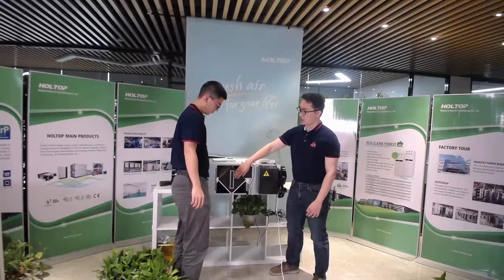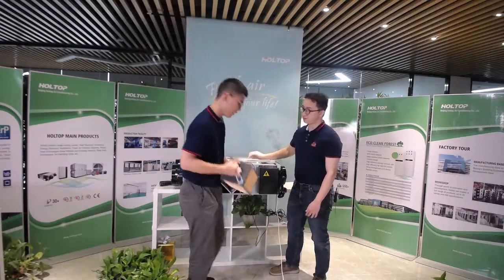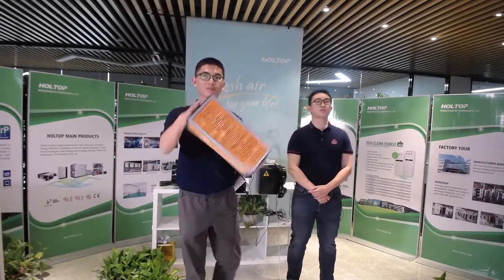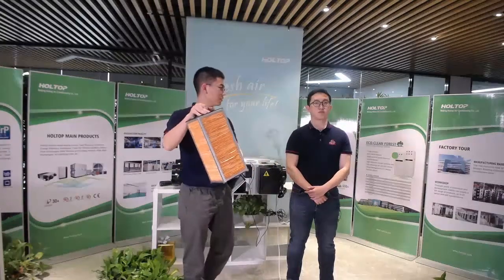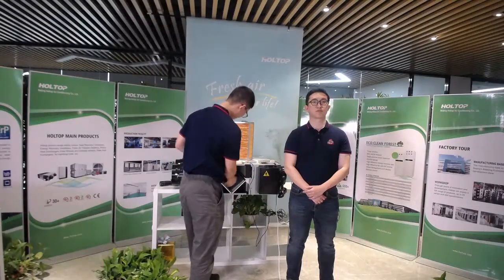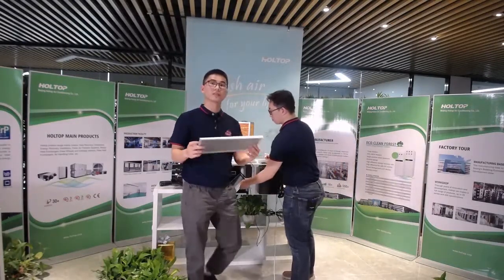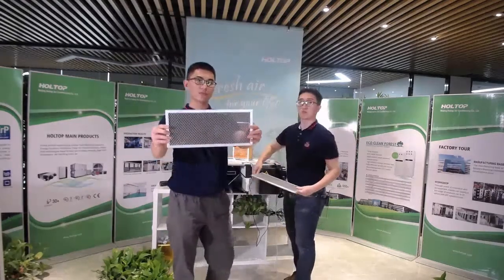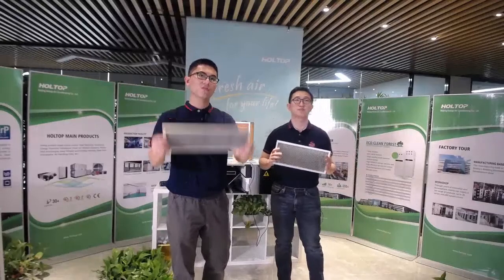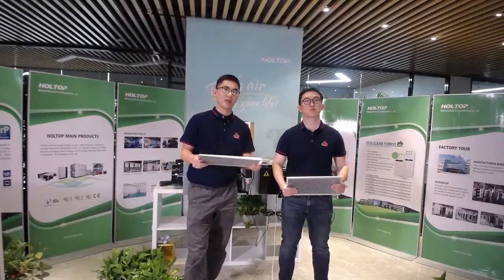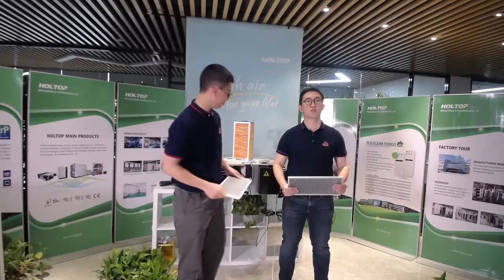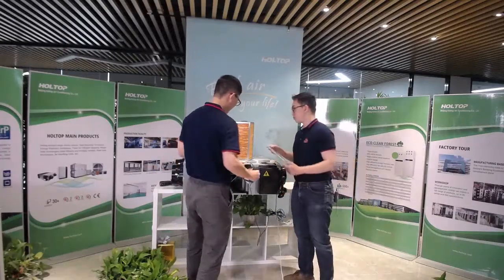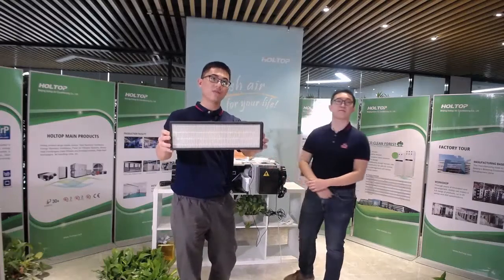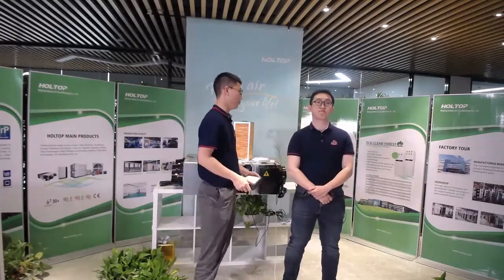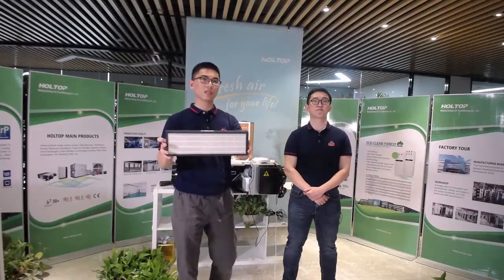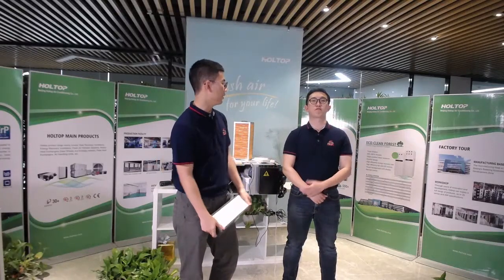This is the heat exchanger, a new generation of ERV paper. Now this is the new framework primary filters - we have two options. For the primary filters, we have optional activated carbon filters and F9 filters. This is the standard F9 filter to remove 99% of PM2.5. For this filter, you can choose a higher grade like H10 and H13.